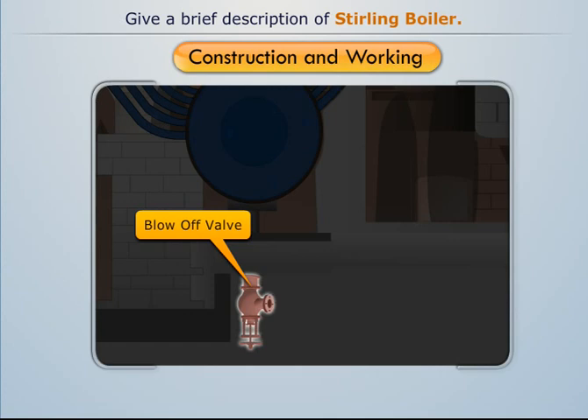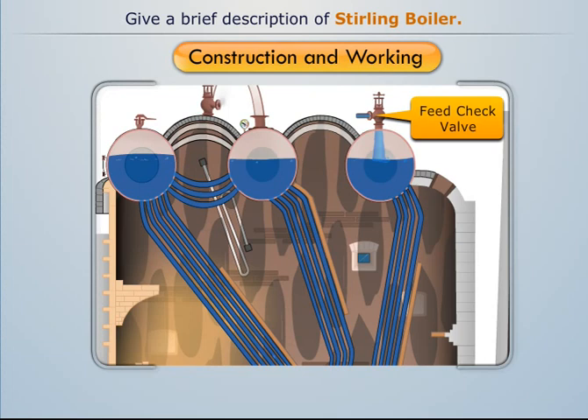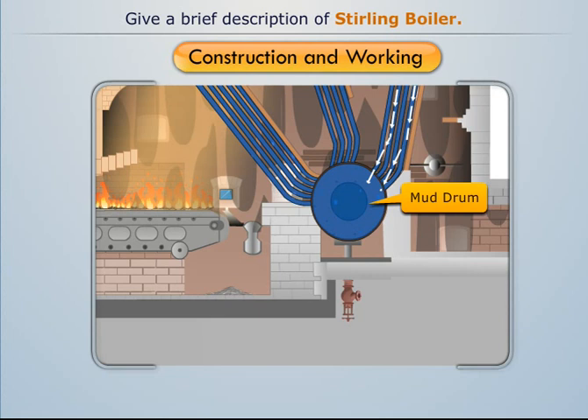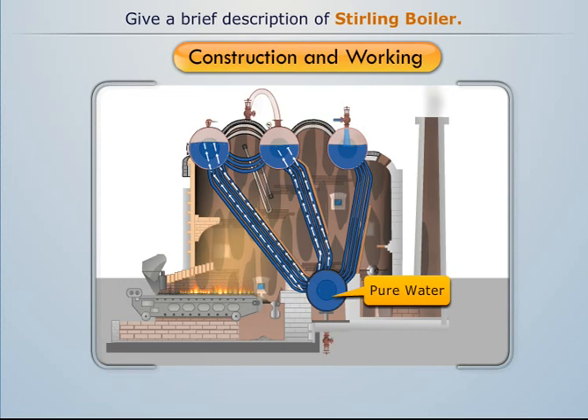Water is fed through the feed check valve to steam drum 3, which then passes through the bent tubes to the mud drum. In the mud drum, the foreign particles get settled down and are removed through the blow-off valve at regular intervals. Thus, pure water passes upwards through the bank of bent tubes to the other drums.